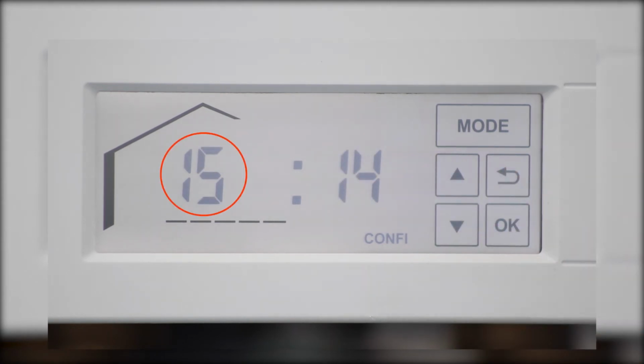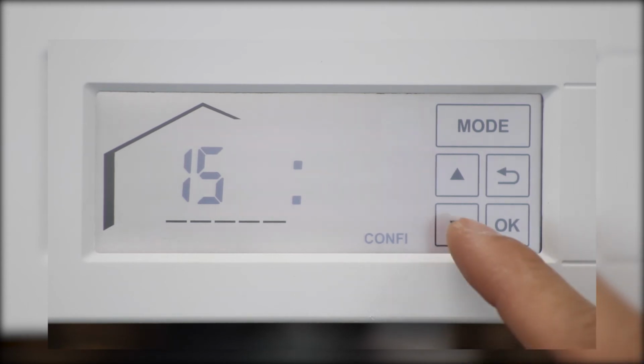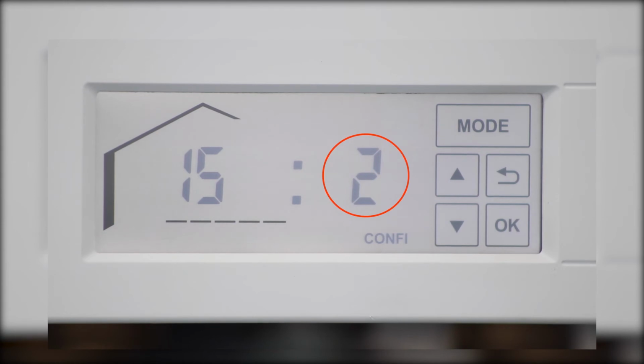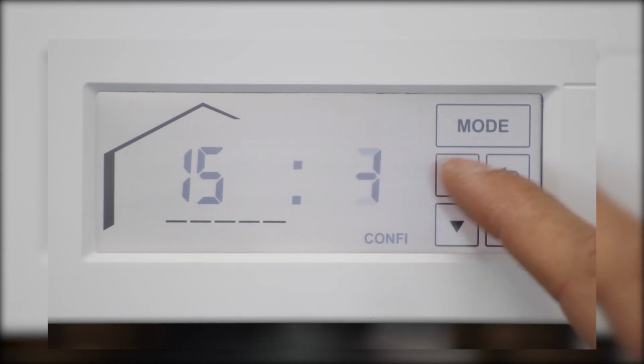Pressing OK on address 15 will allow you to change the value from 2 to 34, representing a 0.2 to a 3.4 heating curve.